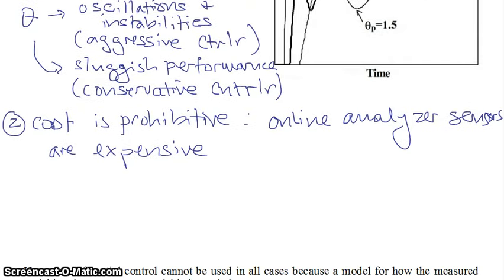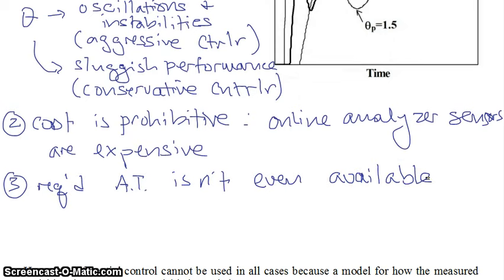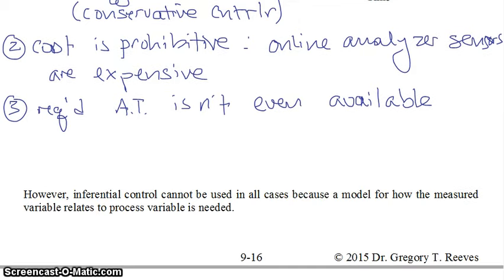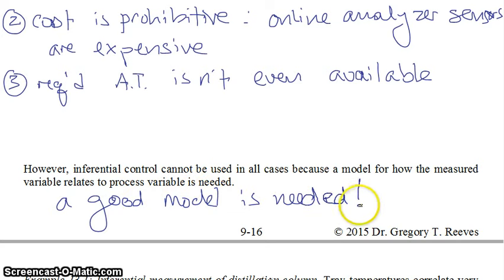Another reason to use inferential control is that the required analyzer sensor transmitter isn't even available — in other words, no one has ever developed a sensor that does that. For inferential control to work, you have to be able to measure one of the easily measured process variables, like temperature or pressure, and relate that back to your composition variable. A good model is needed — just like in feed forward control, you need a good model, and you would also need a good model here in inferential control. So let's take a look at a quick example of that.